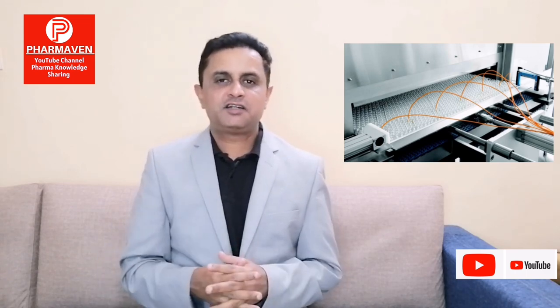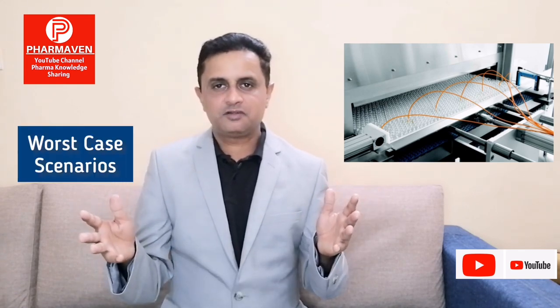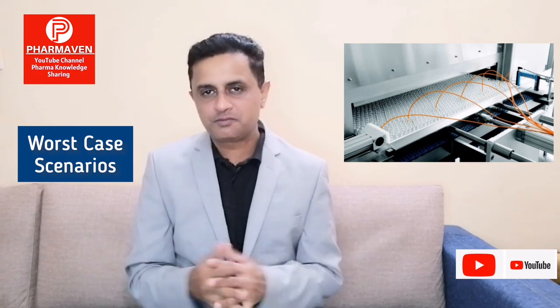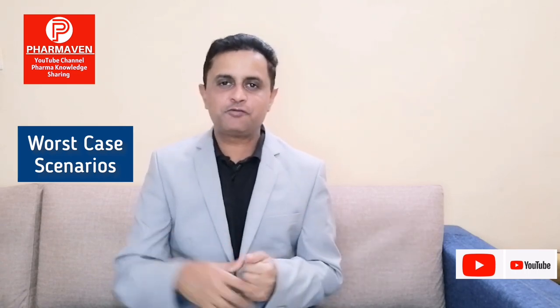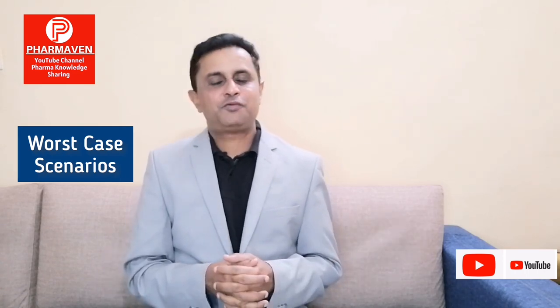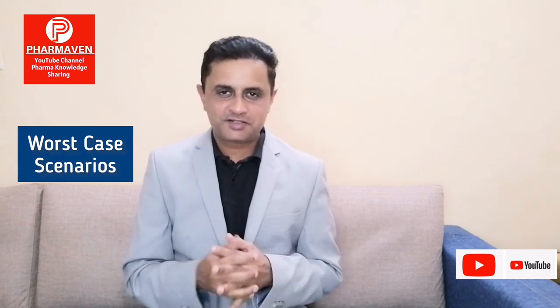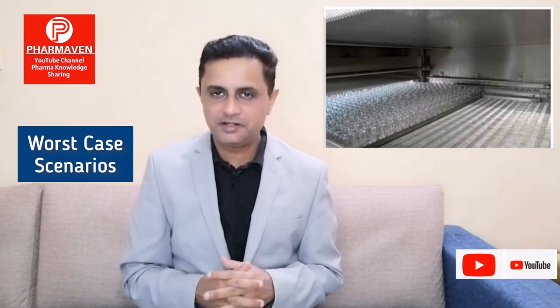Let's first understand what the worst case scenarios in the tunnel are, what the heat distribution problems are, and how we can measure the temperature throughout the conveyor. It's a moving conveyor, so how do we measure, and what is the worst case scenario? For the tunnel qualification, there are three worst case scenarios. First, the very first row of vials which goes inside the tunnel conveyor gets the least amount of heat, and I'll tell you why.